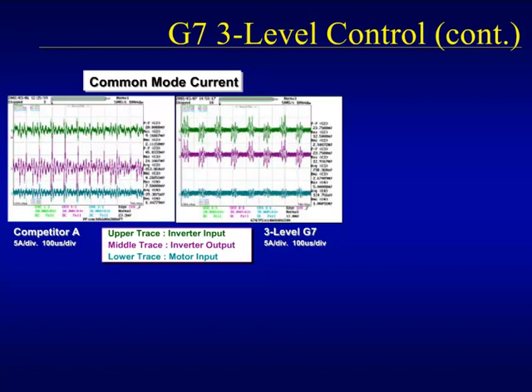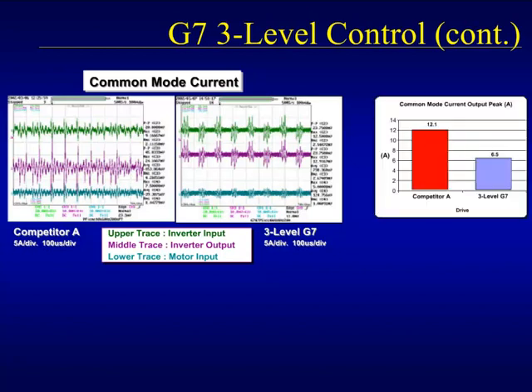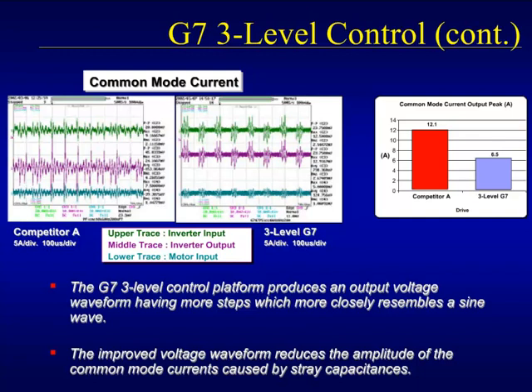Laboratory tests again prove the superiority of the 3-level controlled G7 to that of its 2-level counterpart, this time in regard to common mode noise. Common mode currents, which I have also referred to as leakage currents, are almost cut in half by using the 3-level output voltage waveform. Limiting common mode currents brings about reductions in common mode noise, which in turn makes it safe to use sensitive equipment around the drive.